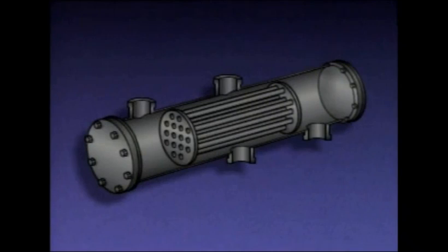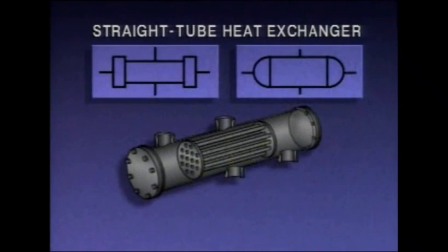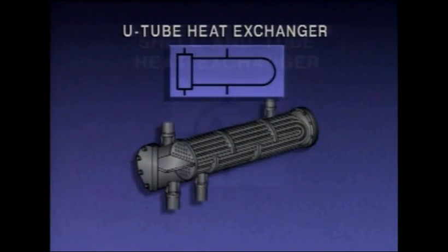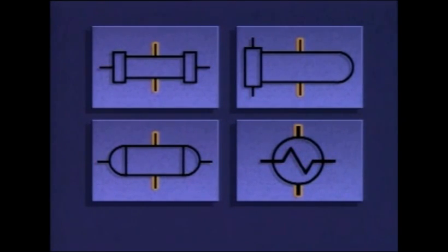In many processes, heat is transferred from one fluid to another, so these processes usually have at least one heat exchanger. In this example, steam is used to heat a process fluid. The process fluid flows through the tubes in the heat exchanger and the steam flows through the shell around the tubes, transferring heat to the fluid. This is a straight tube heat exchanger. These symbols are often used to represent a straight tube shell and tube heat exchanger. Another symbol represents a U-tube shell and tube heat exchanger, and one symbol may represent either type. Each symbol has lines representing the inlet and outlet for the two flow paths — one pair for flow through the tubes and the other for flow through the shell.